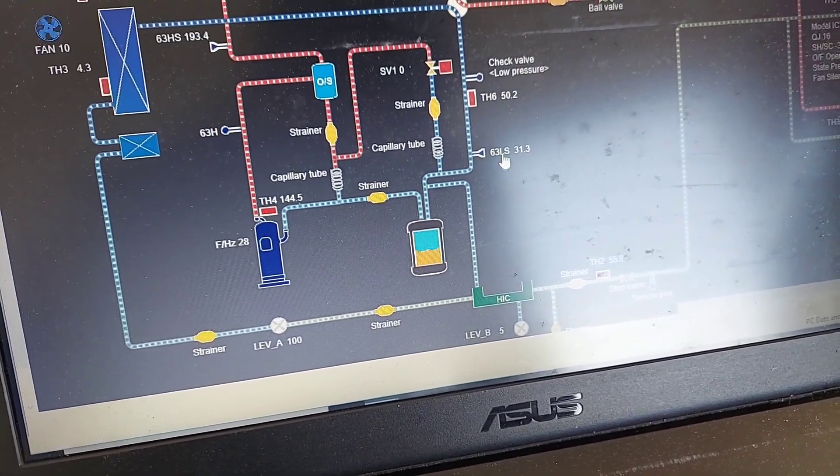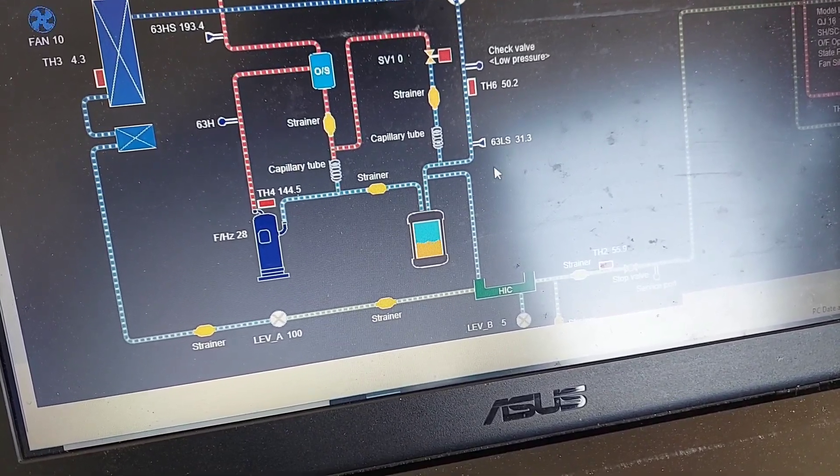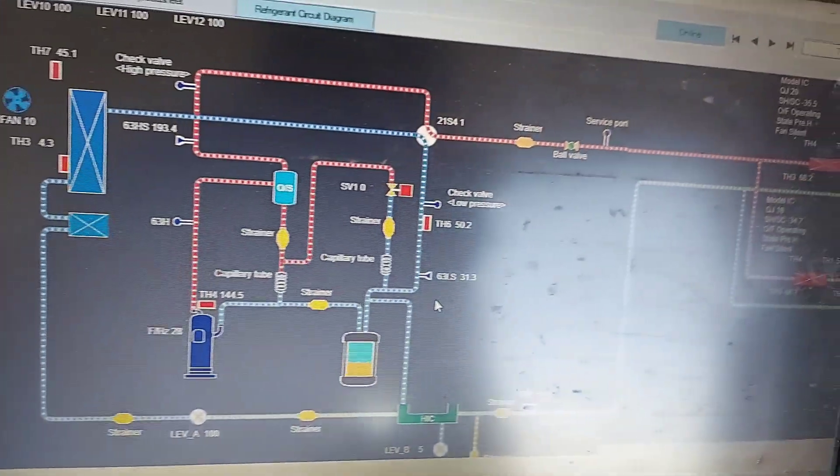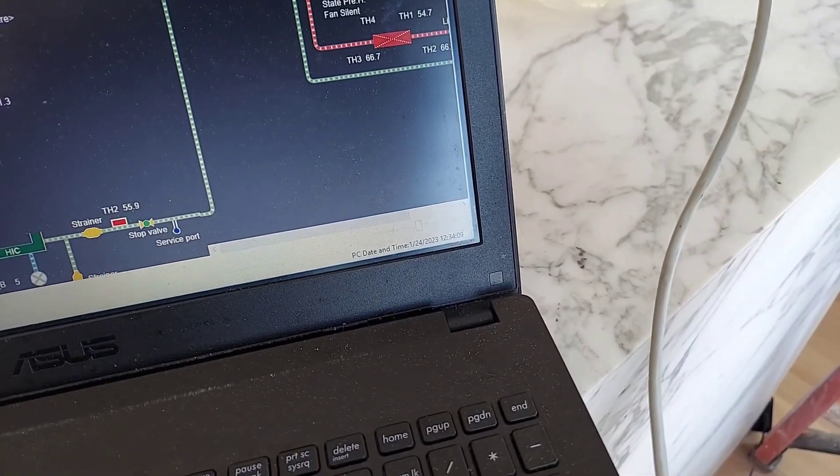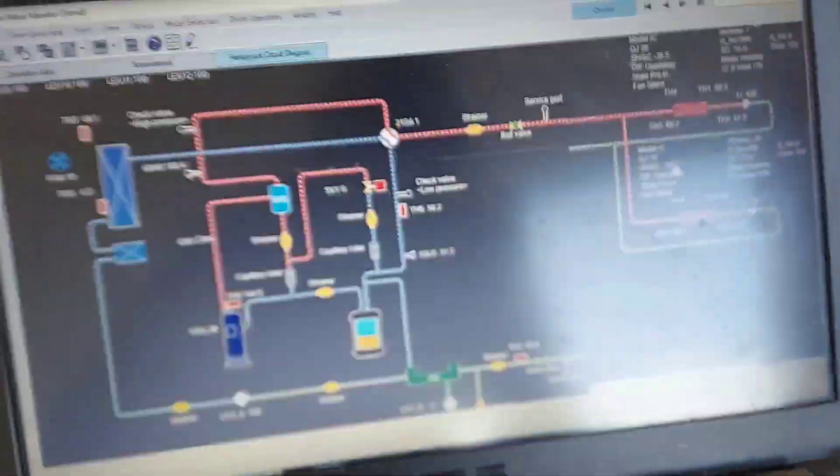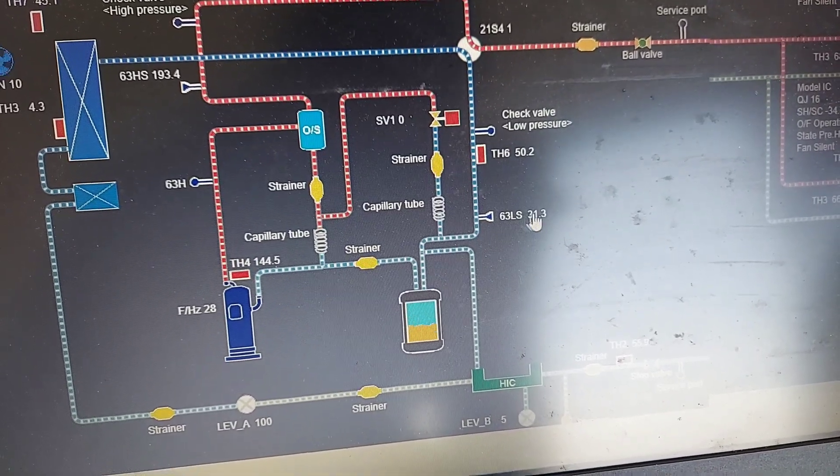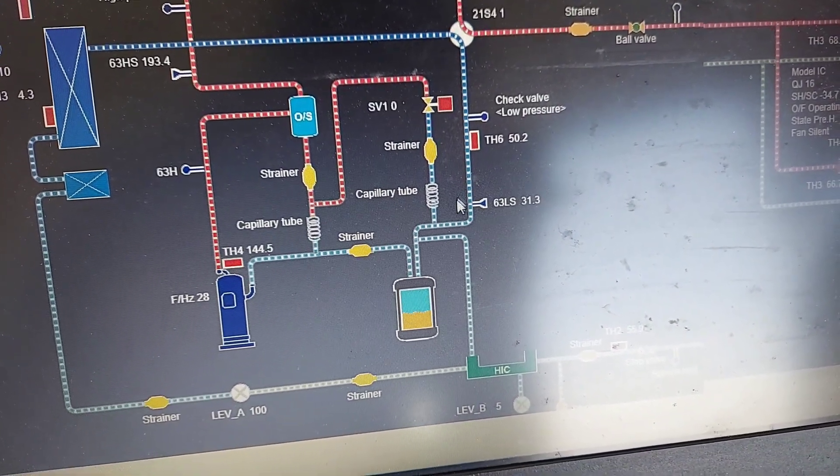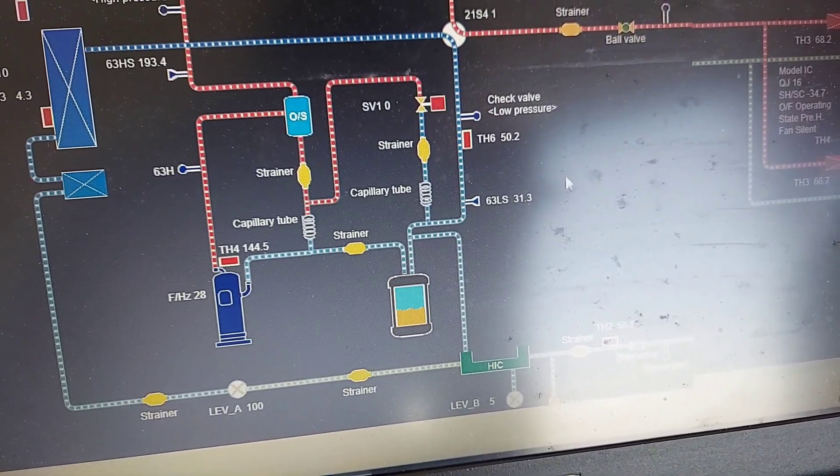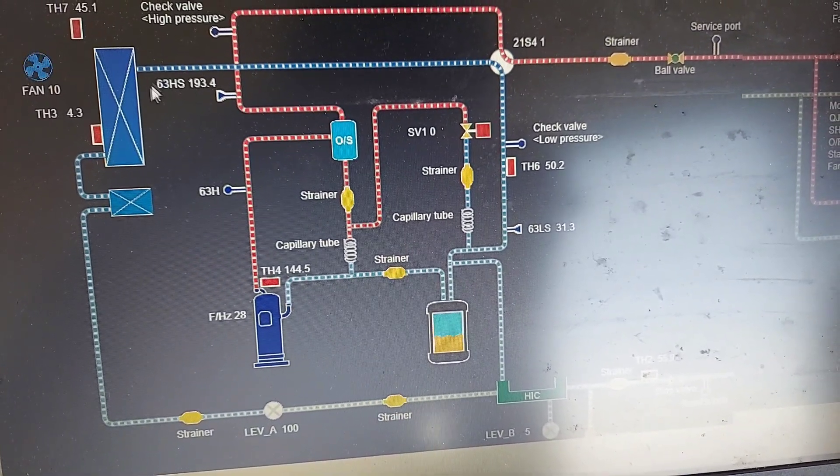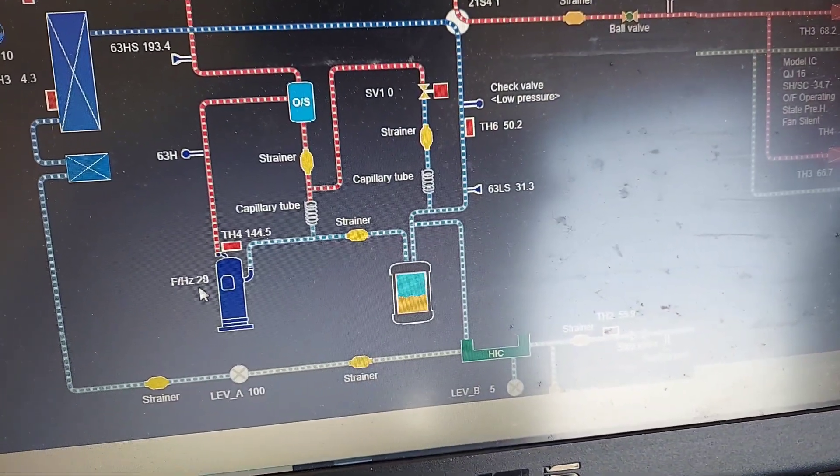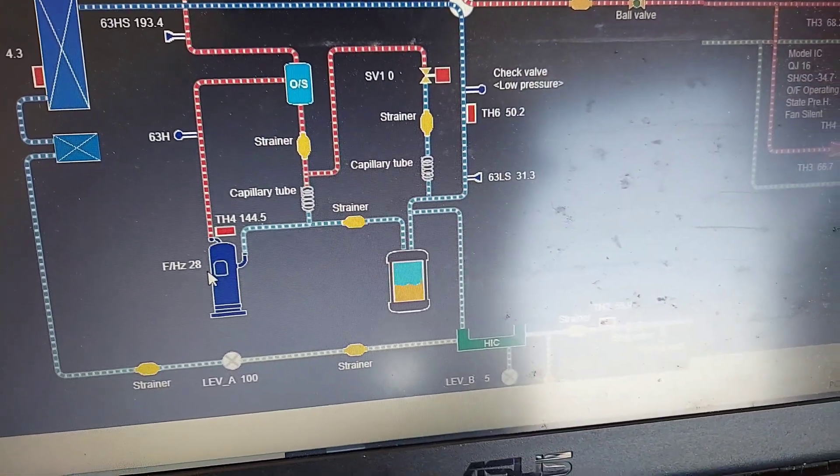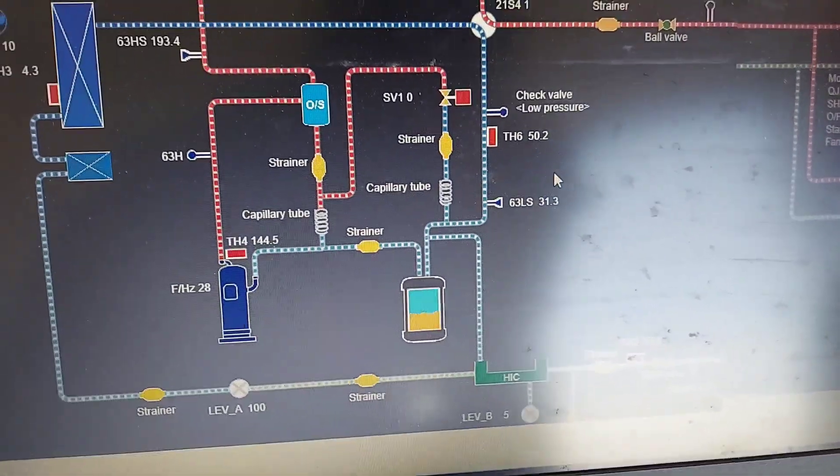But like I said again from experience I know that 1102 is, that error is associated with low on refrigerant charge. All right. So yeah guys, that was the diagnostics. Low refrigerant charge. You can see your back pressure is at 31, I mean that's like R-410A guys, and head pressure only 193 psi, R-410A again, and the compressor is doing at 28 hertz. It ain't going to go any higher because there's no point. It's going to pull into a vacuum if it tries to speed up any further or any faster.